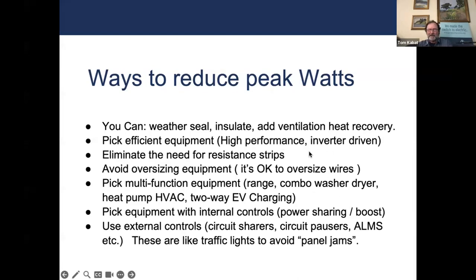Also eliminate that need for heat pump resistance strips - we don't need them in our climate. If you pick a good heat pump, it'll keep up. And avoid oversizing the equipment, but it's okay to oversize the wire.